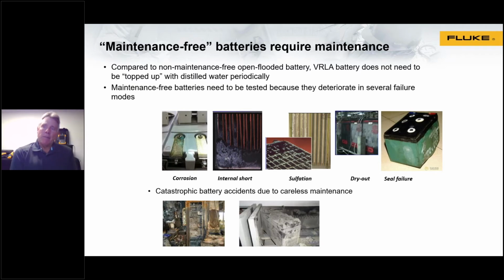Here's why I said maintenance-free batteries, and used air quotes. Here are the real quotes. They require maintenance. So maintenance-free batteries really are not maintenance-free. No, you don't have to add electrolyte to them, but they need to be tested periodically because they can deteriorate over time in a couple different failure modes. And there's some visuals there, namely corrosion, shorts, a process called sulfation, seal failures, and actually due to careless maintenance, you could have catastrophic failures. And there's a couple of pictures that show that.